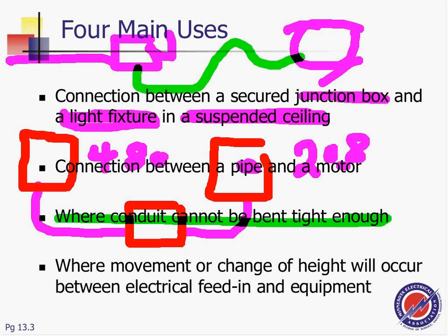It's a transformer. You really don't want to tie it to a transformer because of humming, though you can EMT it. You can, though. It might not be a whole lot of vibration, but it's a good idea to use a flex with a few of these, especially bending conduit in a small space, really hard to bend there. That's a good application for a transformer here.